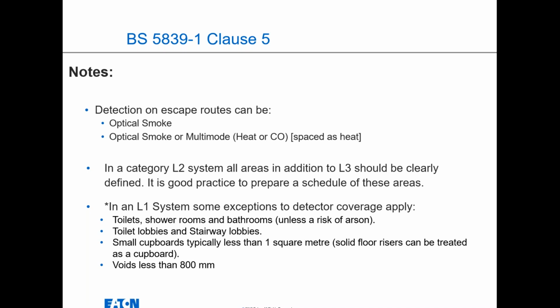There are some exceptions. So you can basically risk assess out toilets and shower rooms and bathrooms, lobbies, stair lobbies, small cupboards less than 1 meter squared, and voids that are less than 800 deep, if there are any voids within the building. You still require sounders in those areas, so you still need to achieve a certain decibel level, which I think we'll come on to later, but you don't necessarily need detection.